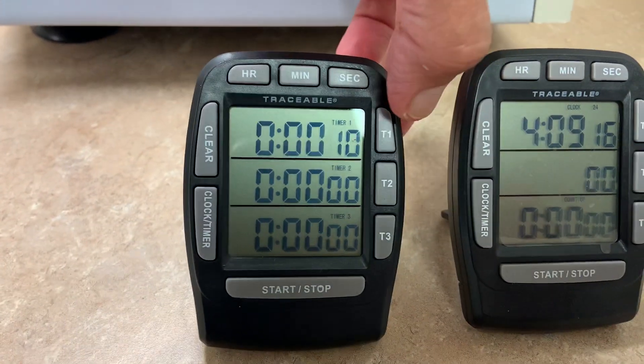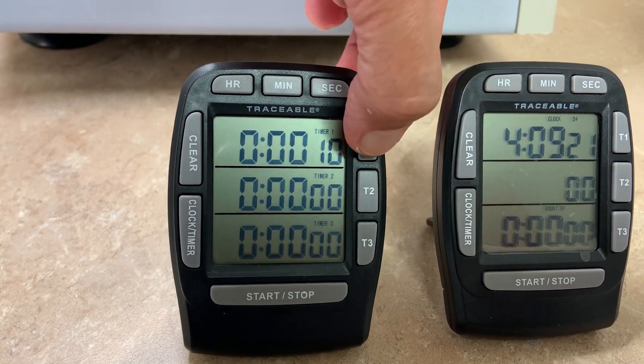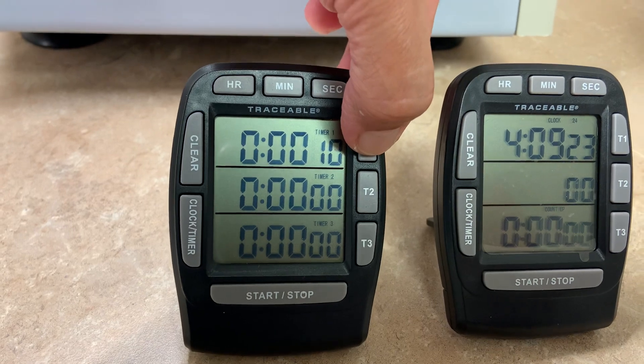Press the same channel button again twice — the first press is to stop the flashing, and the second press is to start the countdown.